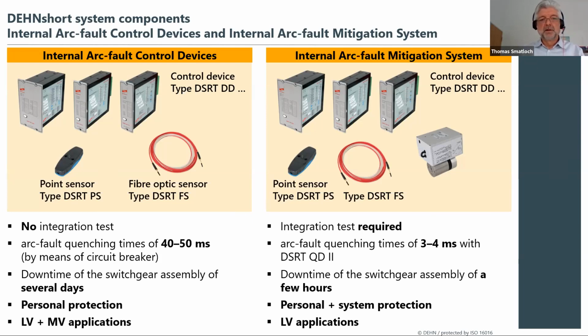So on the left-hand side, the downtime of the switchgear assembly after such an event is several days, and the device, due to the quenching time, delivers personal protection and can be used in low voltage and medium voltage applications. Compared to this, on the right-hand side we have an instrument with similar controllers in combination with sensors for light: different shapes of light sensors, punctual sensors, and this fiber optic sensor to be connected with a controller. And in this case, we have a connection to an active device. So that's why we call it an arc fault mitigation system.